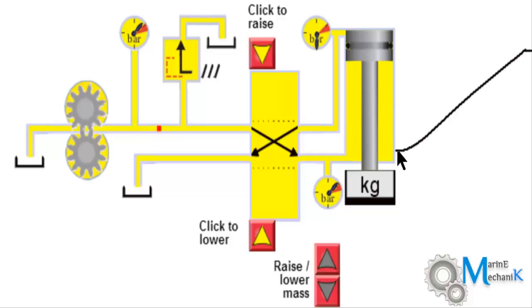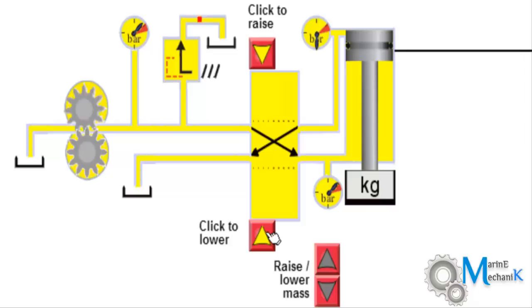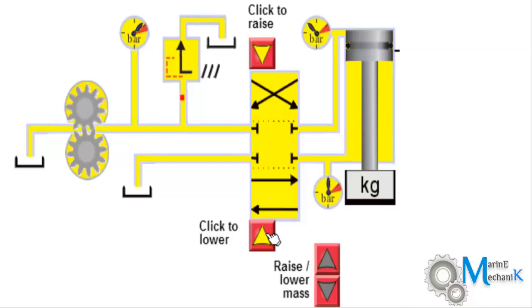Now on looking at the graph, this shows the rate of rise of pressure to complete the work done in lift of the piston for this particular weight. Now I am going to put it back to neutral position where the pressure drops immediately because there is no more flow of oil as all the ports have been blanked.